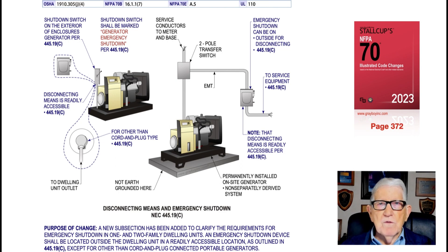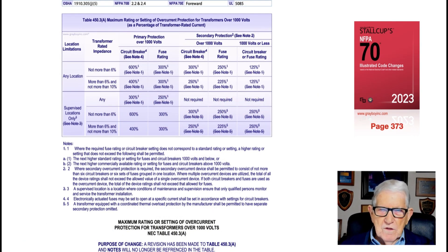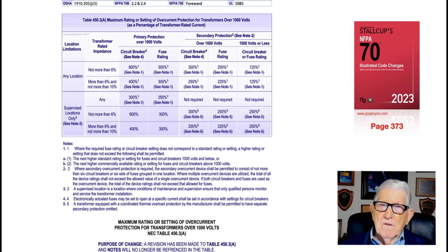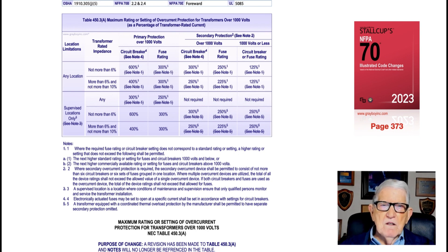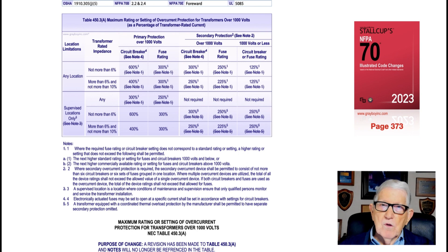This illustration deals with the maximum rating or setting of an overcurrent protection device for transformers rated over 1,000 volts in accordance with 450.3(A) and Table 450.3(A). Notice that revisions have been made within the table itself — Note 1 has been deleted in various columns. You still have unsupervised locations, and then supervised locations where you can see revisions taking place. Revisions were also made to the notes below the table, so users should review those notes to see where they apply.